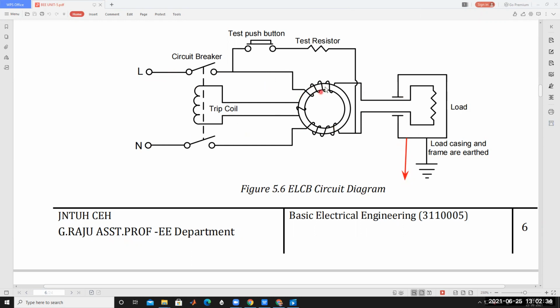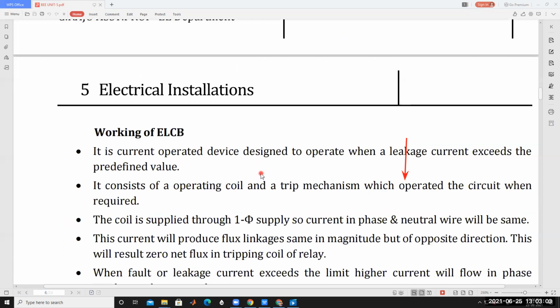So here the coil is induced by 5 amps, and the other coil is induced by 3 amps, because the remaining 2 amps is flowing to the ground. That's why there is a difference between the two fluxes. The flux from 5 amps is greater, and the flux from 3 amps is less. That's why the resultant flux is not 0. The resultant flux flows to the trip coil, and the trip coil is activated and opens the contact. In this way, this ELCB operates.